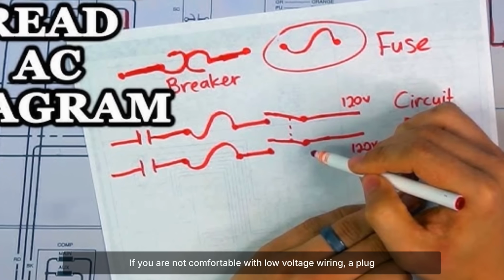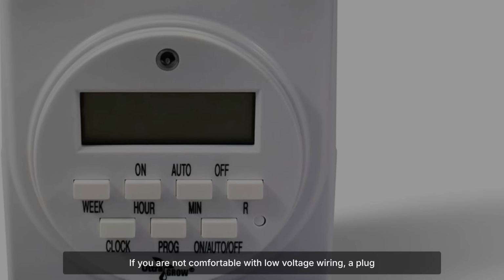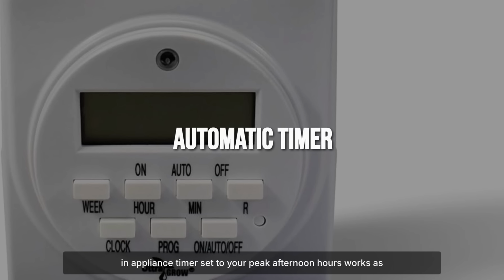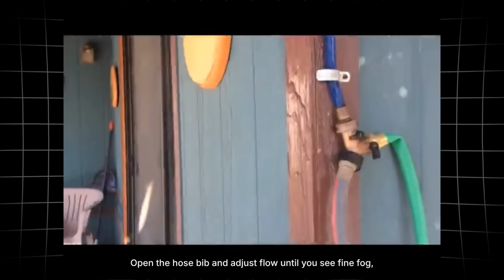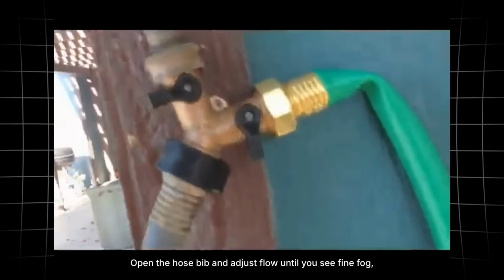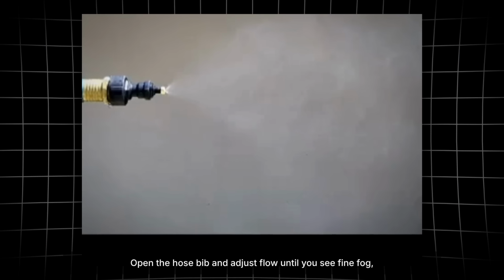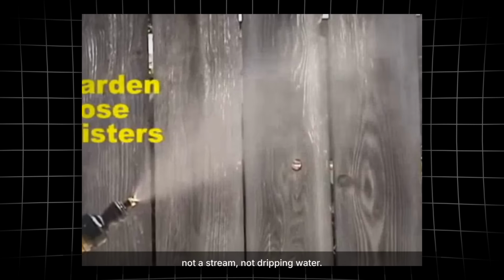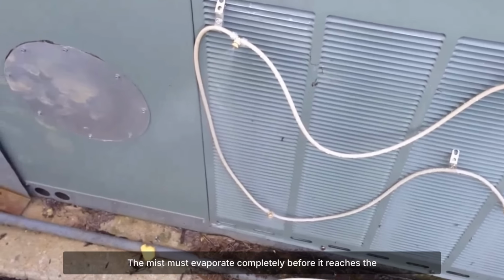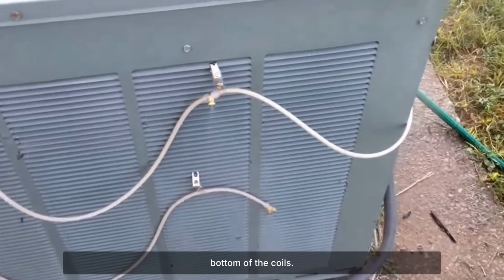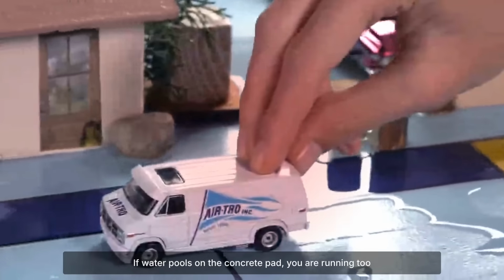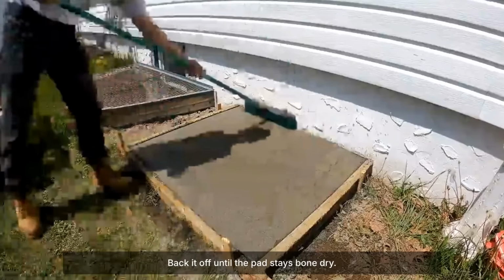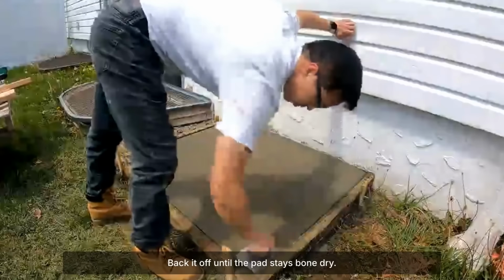If you're not comfortable with low-voltage wiring, a plug-in appliance timer set to your peak afternoon hours works as a simple alternative. Open the hose bib and adjust flow until you see fine fog, not a stream, not dripping water. The mist must evaporate completely before it reaches the bottom of the coils. If water pools on the concrete pad, you are running too much. Back it off until the pad stays bone dry.